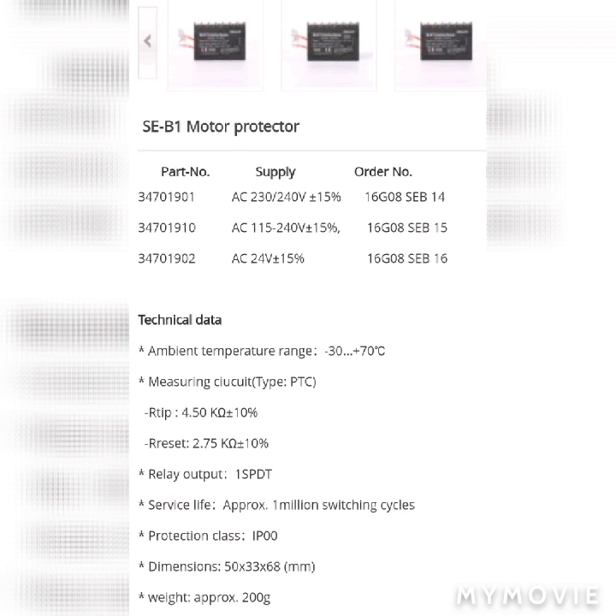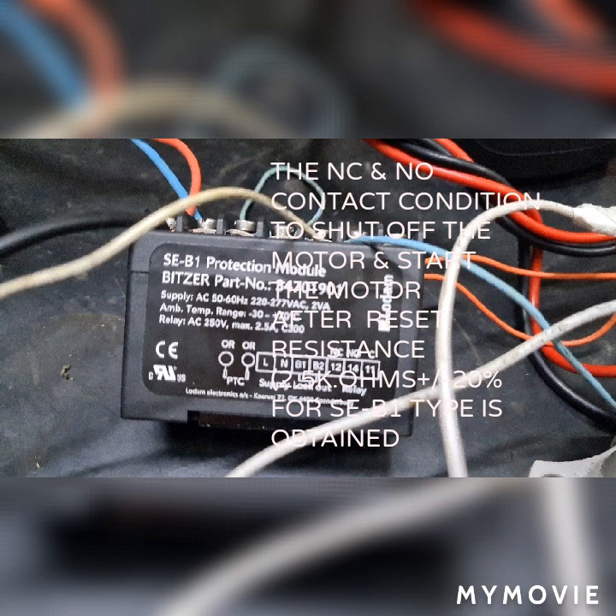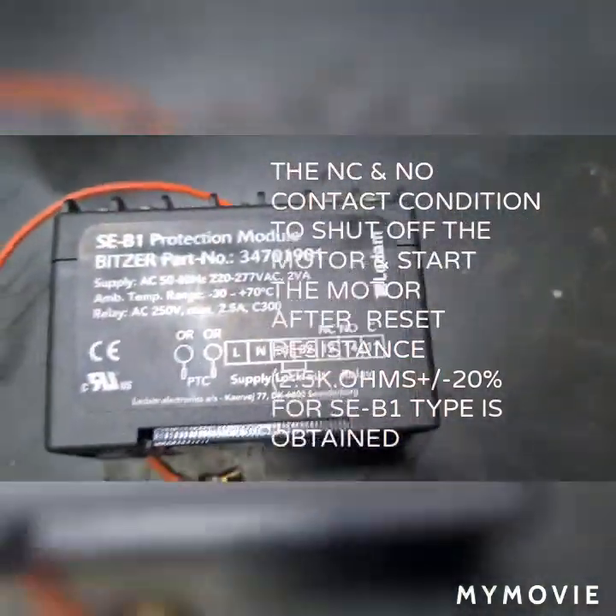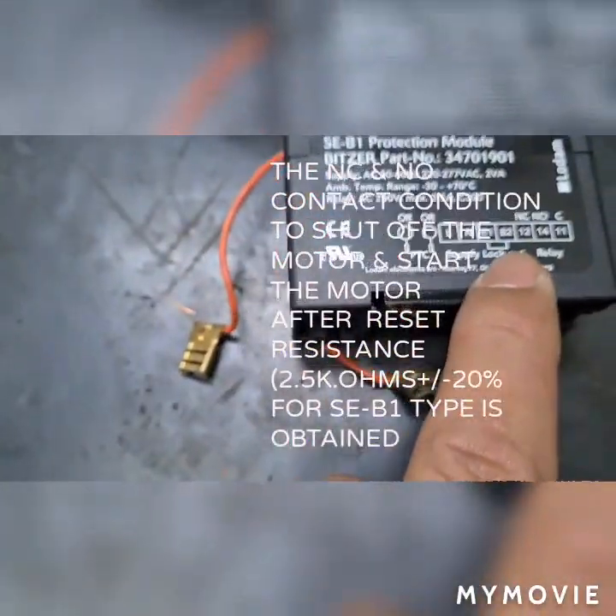Normally this SE-B1 type motor protector will change its state from normally closed to open when the resistance of your coil winding has a value of 4.5 kilo ohms, and it will automatically reset itself when the temperature of your motor becomes less, giving an equivalent resistance of 2.5 kilo ohms.